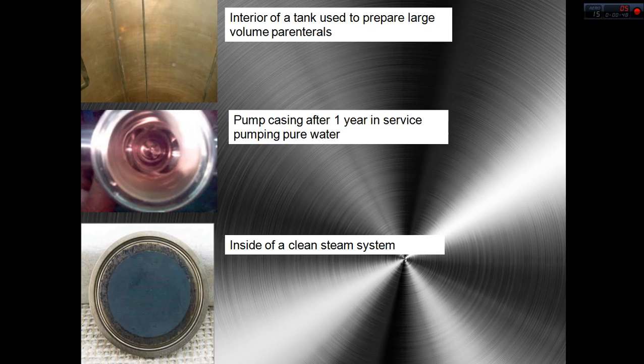Yes, I know that 'stainless' means no stain, but that's not always the case. As we can see in the top picture, that's the internal surface of a tank used to prepare parenterals, and the red color is iron oxides. In the picture in the middle, the red color is again iron oxide, and that picture came from a pump that was pumping pure water. At the bottom we can see a black residue, which is also iron oxide — it's just that the composition, the relation between oxygen and iron in this oxide, is different. That sample was taken from a metal piece in contact with pure steam.